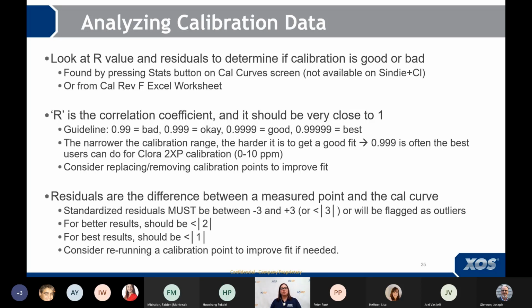Okay, and then how do you improve your correlation coefficient? What you can do is consider replacing or removing points to improve the fit. Sometimes you just get a bad calibration standard. It happens. So you can actually remove that and you will improve the fit of your calibration. Oftentimes, though, what people want to do is replace it using that replace feature. But which ones do you replace? You look at your residuals for this, okay? And the residual is the difference between the measured point and the calibration curve.